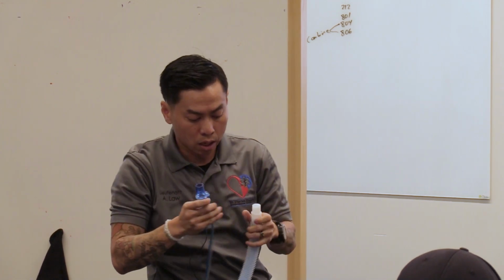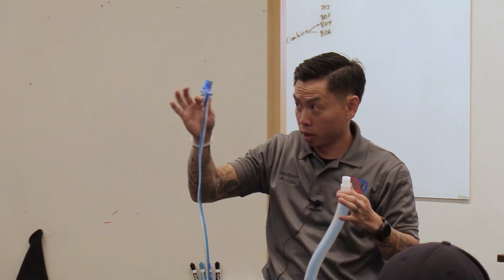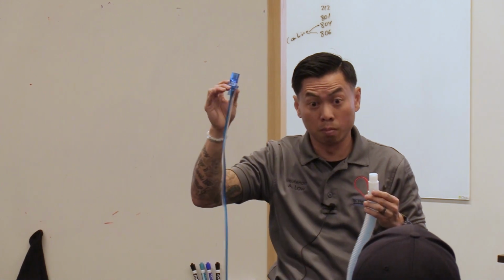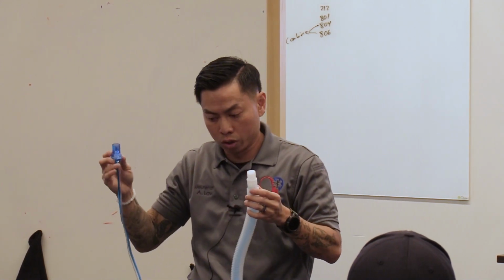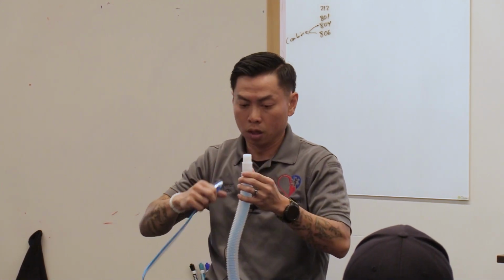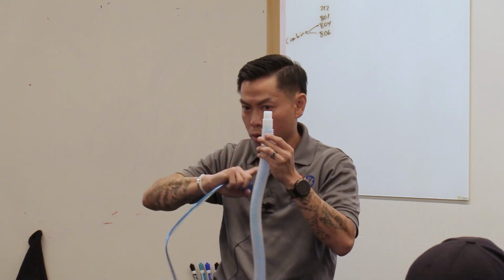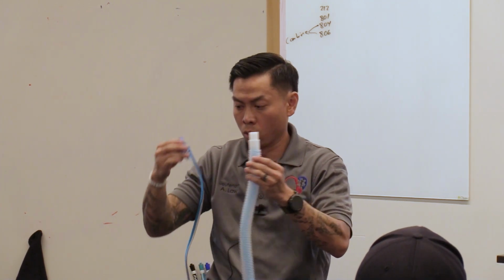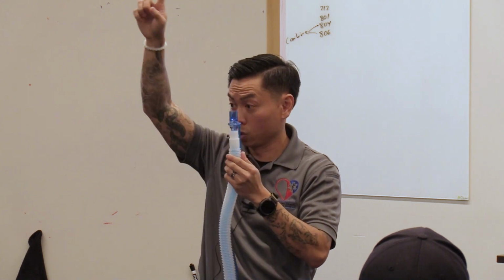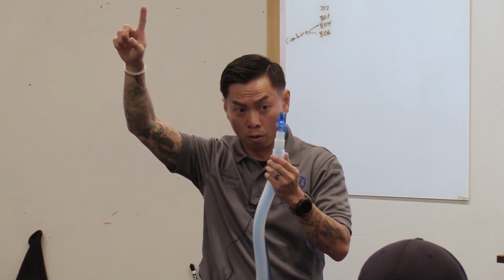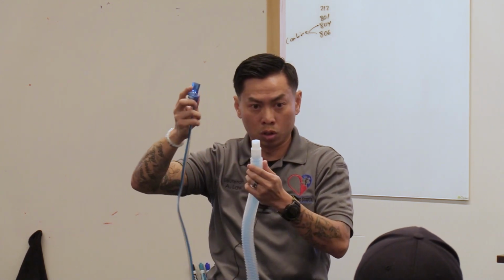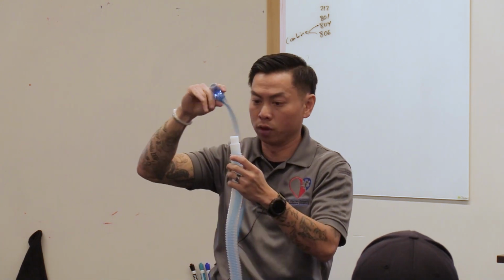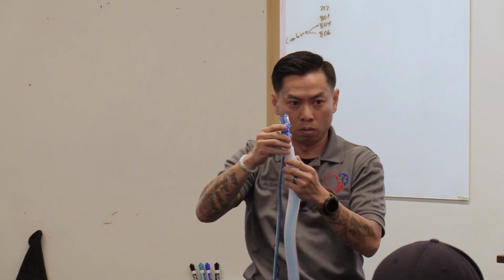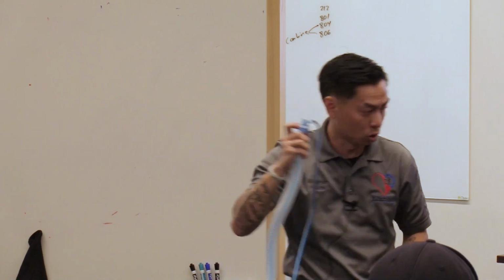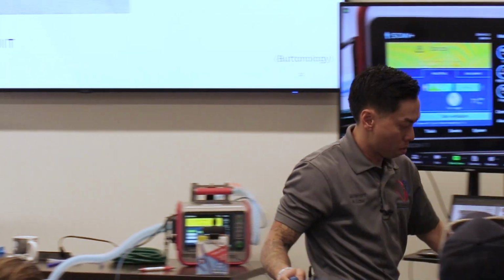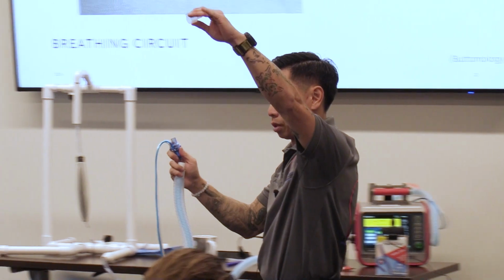So when I say that, we have to do a flow sensor check, right? We're checking to make sure that this thing is working and measuring properly. So in order to do that, we have to put air through it. Air only goes one direction through this circuit, right? And so when you have it like this, yes, it'll send the inhalation phase and measure it appropriately. But then when it wants to test the exhalation measurements, you have to turn it around, but it doesn't go on, right? And so that is where this adapter comes into play.